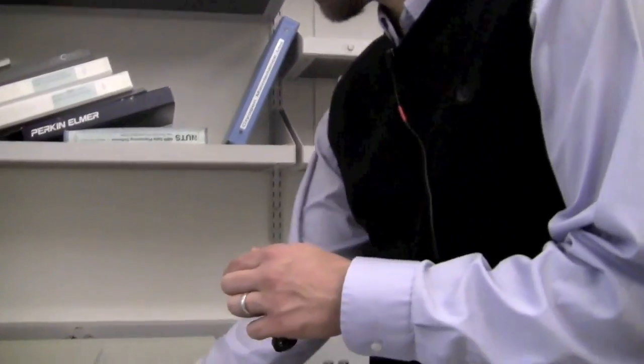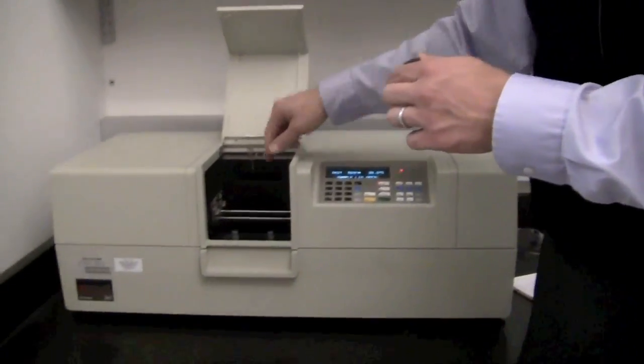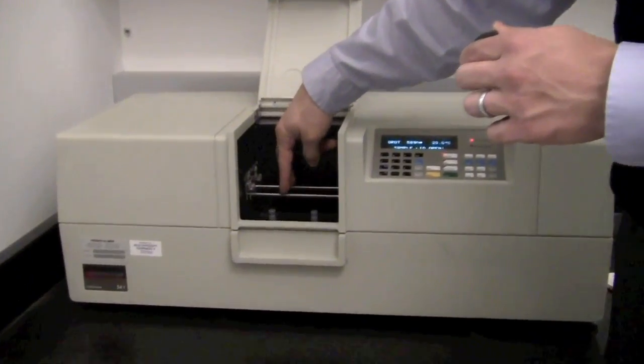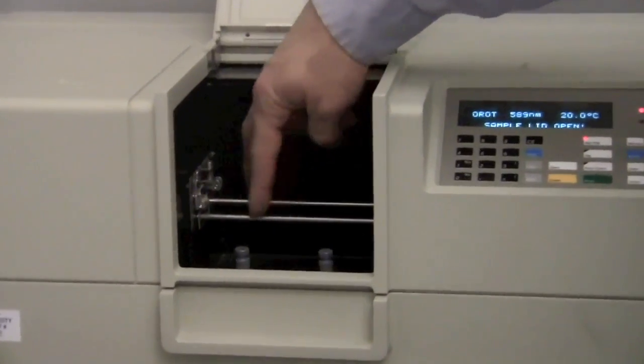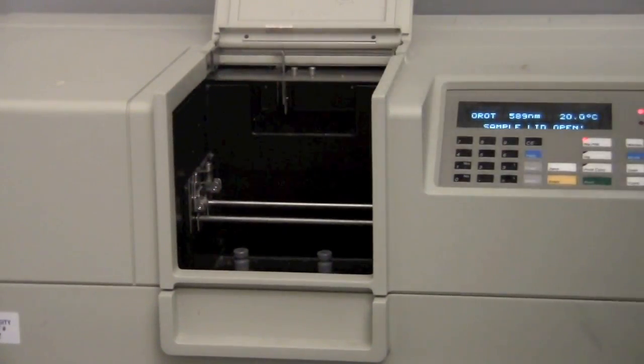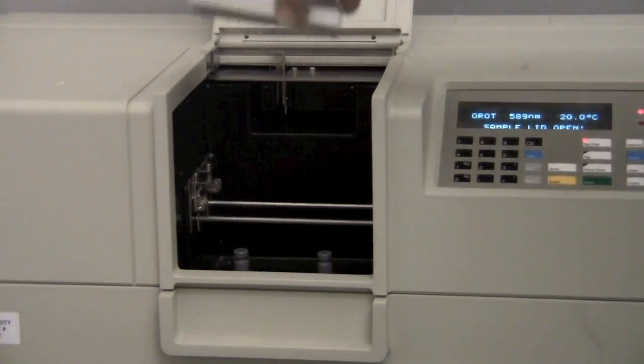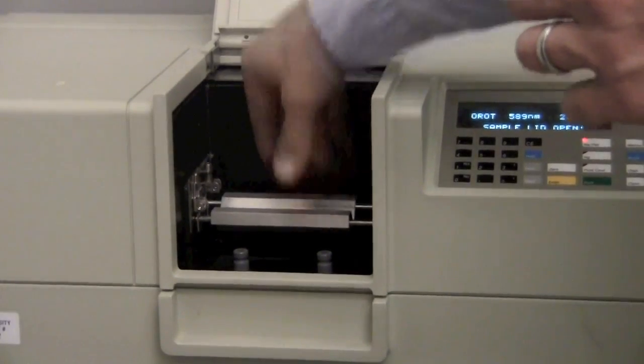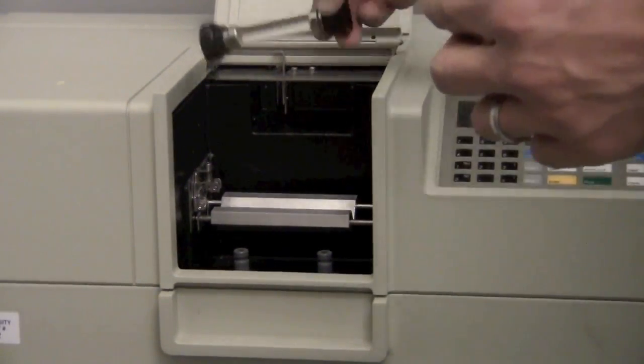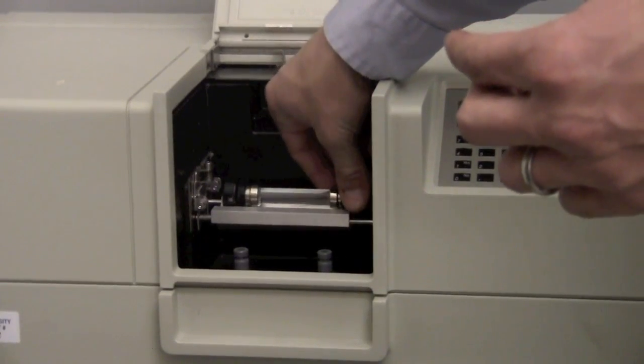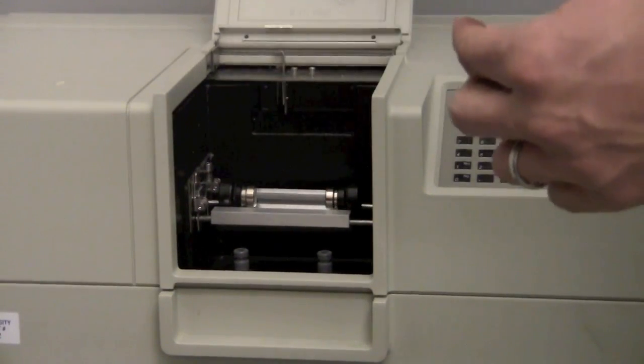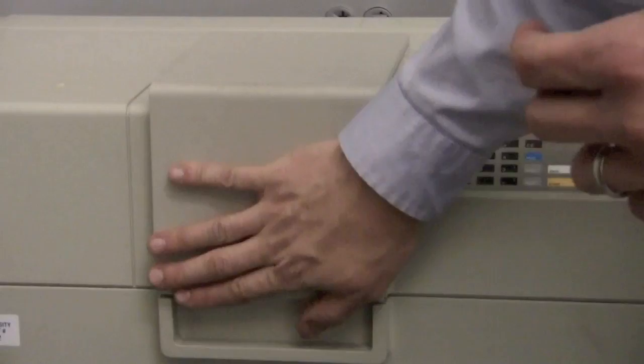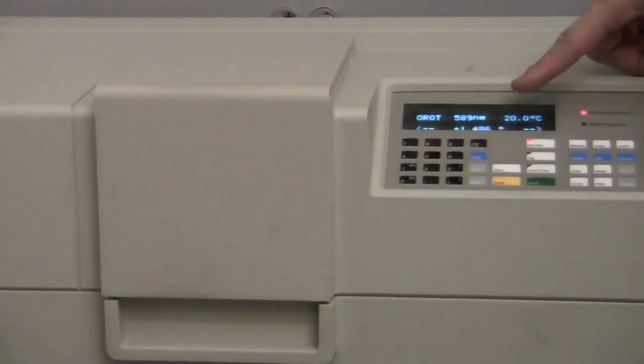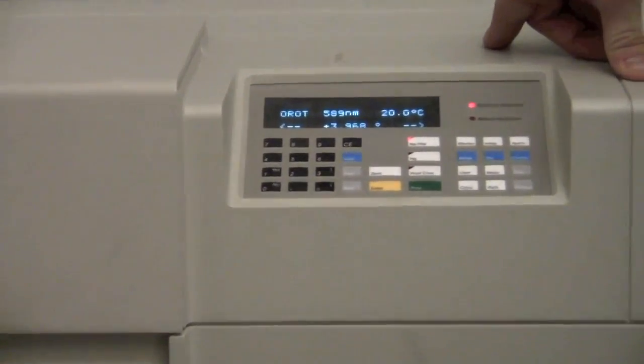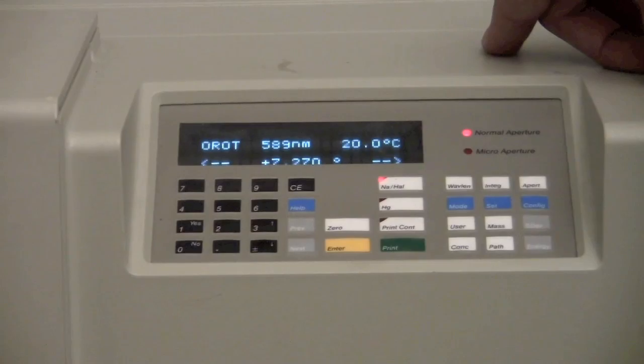Once you've got the sample in the cell and filled, you'll want to put it into the instrument. So you open the door. The larger cells can sit directly on these rails here, but for the smaller cells, you'll want to use this aluminum holder and just put the sample cell in the holder, close the door, and it will adjust to figure out the rotation.